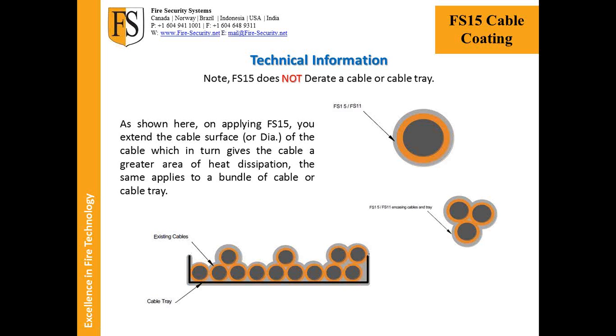It does that without any issue. So our FS11 cable coating, our intumescent cable coating, also doesn't derate your cable system. Obviously, if you put 40mm of the coating on top of it, you are creating an extremely heavy blanket, and you're not giving the cable the ability to breathe. But at its regulated thicknesses of 1 or 1.6mm, there's no issue. It doesn't derate your cable system, and in some respects you may find that a greater amount of heat is dissipating out of that cable, more so than before, because your surface of dissipation is greater.